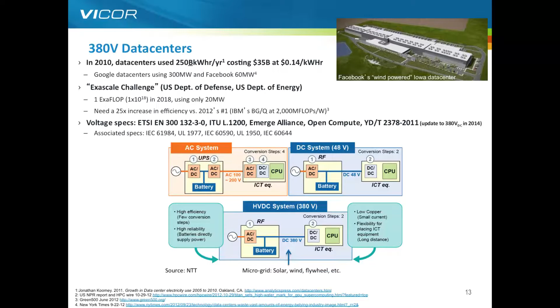So we take in AC from the very high voltage outside the walls as it's delivered by the power company. But once we convert that down to a high voltage DC 380, and at that point do battery backup, we keep it at 380 volts until we need it. So that's how the high voltage DC system came about.